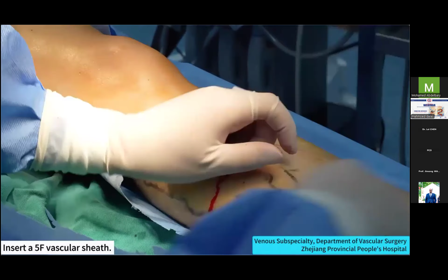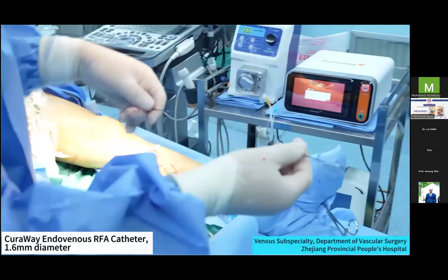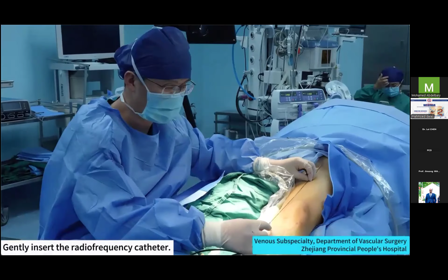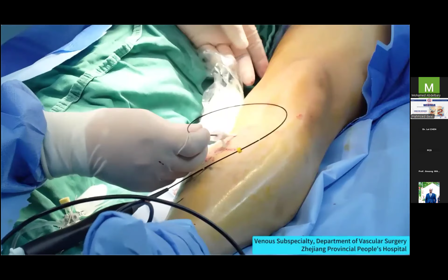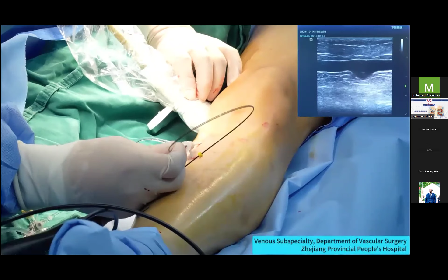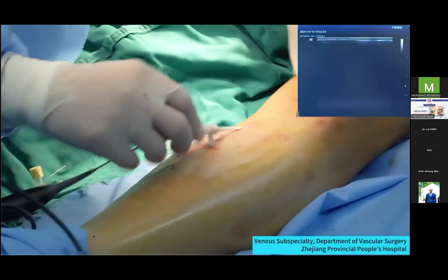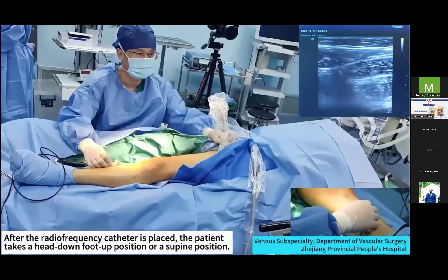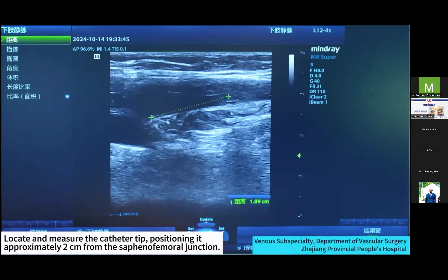Insert a 5F vascular sheath. Curaway endovenous RFA catheter, 1.6 mm diameter. Measure and locate the catheter insertion length in vitro. Gently insert the radio frequency catheter. Push the catheter under ultrasound guidance. Use hands to gently pull the catheter through smoothly. After the radio frequency catheter is placed, the patient takes a head down, foot up position or a supine position. Locate and measure the catheter tip, positioning it approximately 2 centimeters from the saphenofemoral junction.